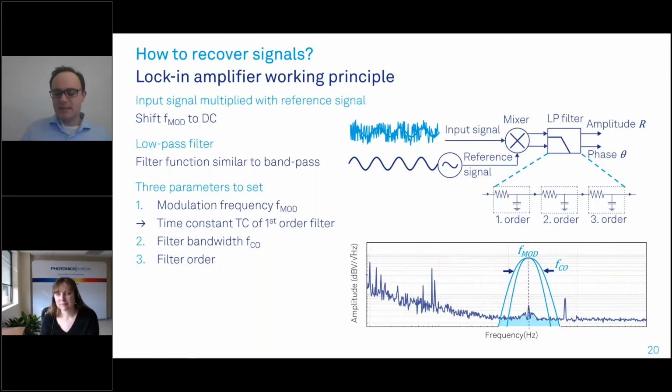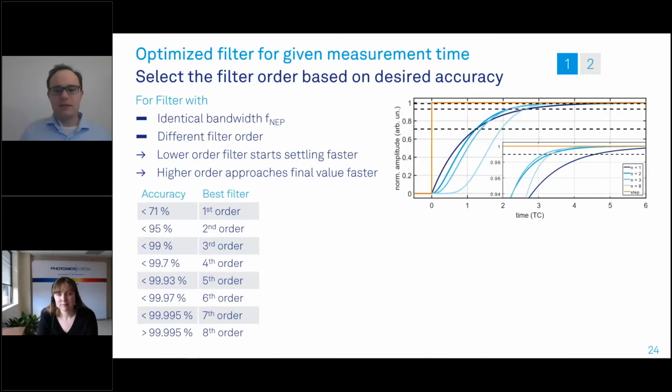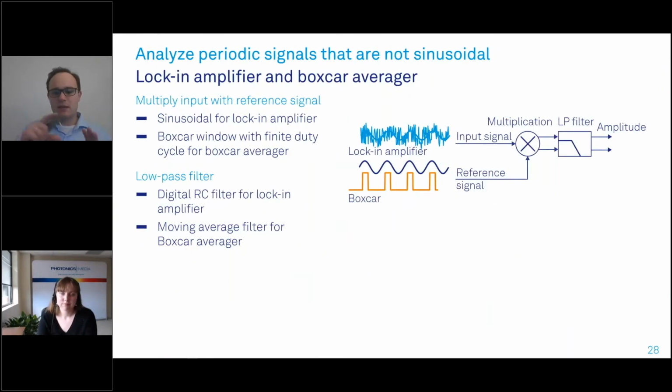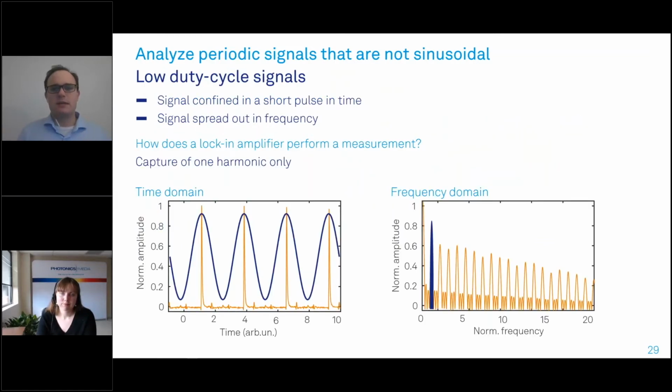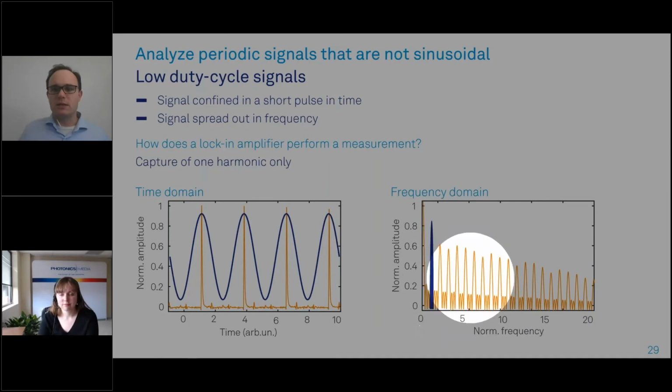So this is a really great question, because I will just quickly jump to the slide to answer it. I assume the question aims at the harmonics which I show in this image. And yes, the lock-in can detect the first harmonic. Maybe it's a user of one of our instruments, who knows, we can even detect up to 8 harmonics. So of course you can take a lock-in and detect not only the first harmonic, but also the next, another one, and so on.